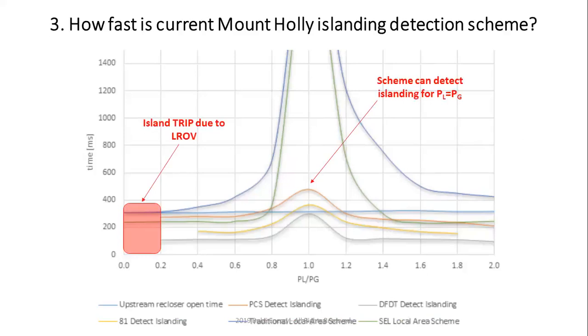We have tripped every single time. We have tested this probably about 30 times, and we have proved that there's something called load rejection over voltage. When you have a whole lot of generation and you do not have a lot of load, essentially in this case meaning somewhere close to infinite generation, the battery inverter is going to trip on its own. Why? Because it does not have enough time to change its voltage and frequency based on even its settings.